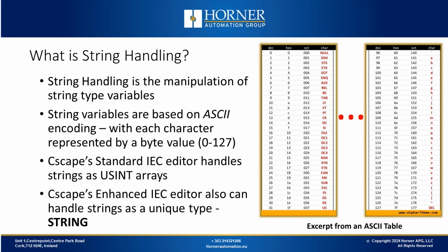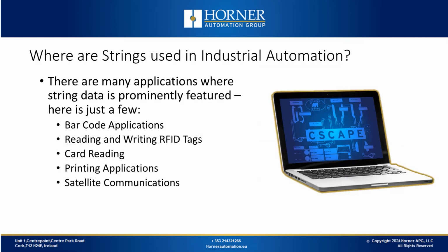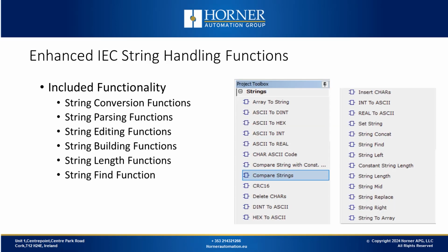The standard IEC editor handles strings as unsigned short integer arrays. The Enhanced IEC editor can also handle strings as arrays, as well as handle strings using the string data type. There are many applications of string handling where it is a crucial aspect of the control. These include barcodes, reading and writing RFID tags, magnetic card readers, printing to serial, USB-based printers for receipts, and satellite communication. Now we will look at the string functionality available in Enhanced IEC.